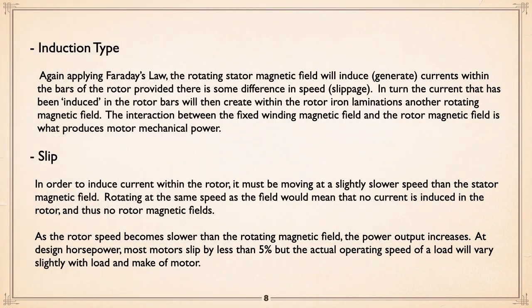Now, induction motor. Faraday's law says you will generate currents within the bars of a rotor, or anything, provided there is some difference in speed. In turn, the current induced within the rotor bars will then create a magnetic field within the rotor. Since you've got a magnetic field outside that's turning and a magnetic field inside, the two either attract or repel at different spots, and the rotor tries to match what the stator's doing.